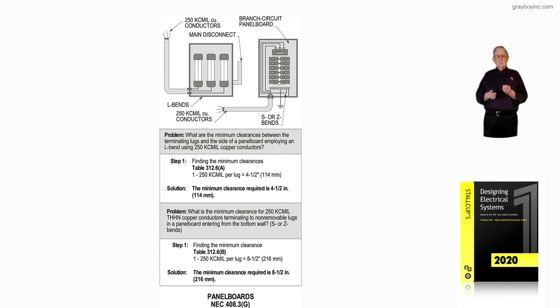Using the same size conductor, 250 KC mill per lug, eight and a half inches is required from the termination of the lug down to the bottom of the enclosure.